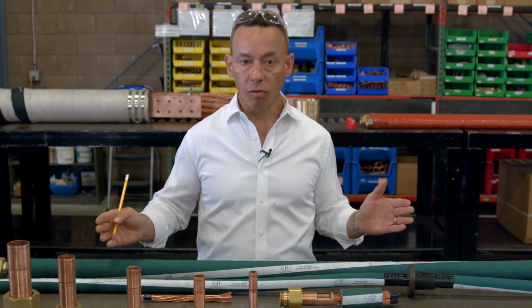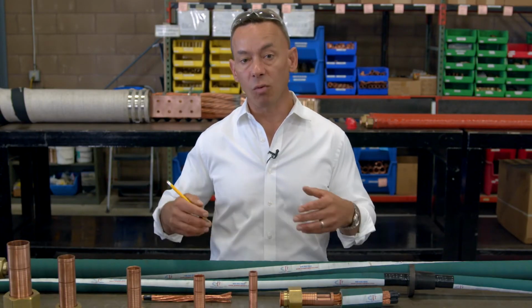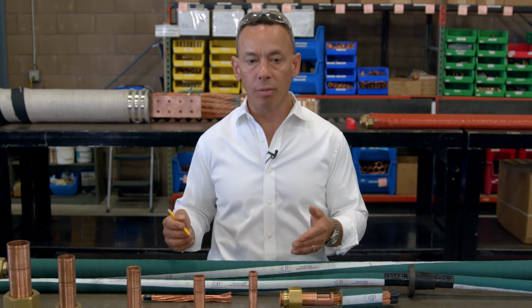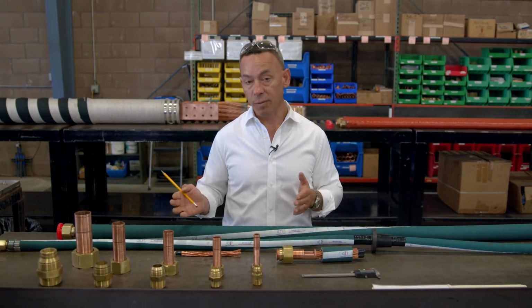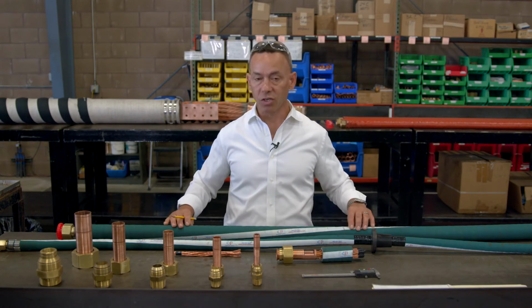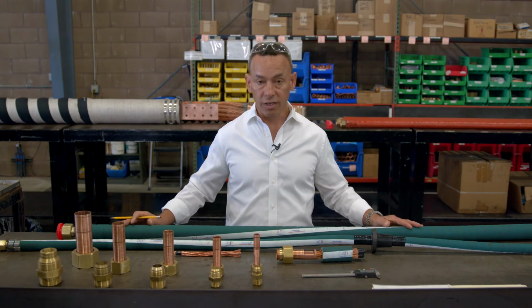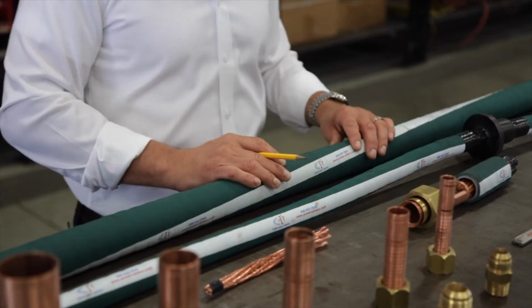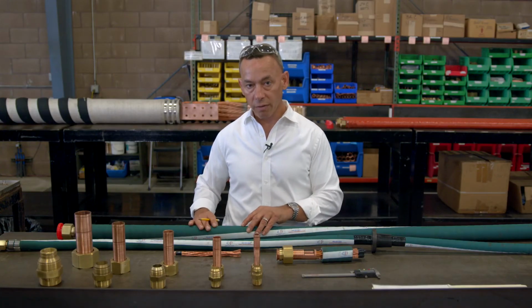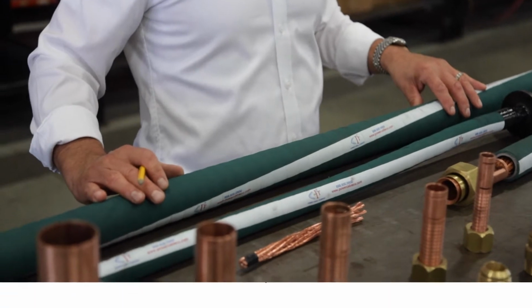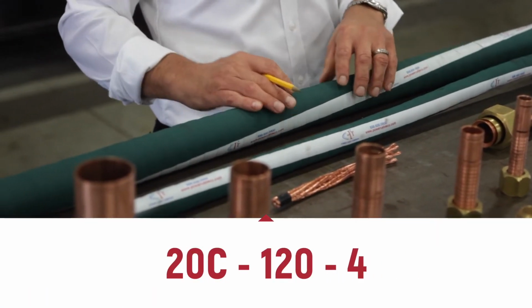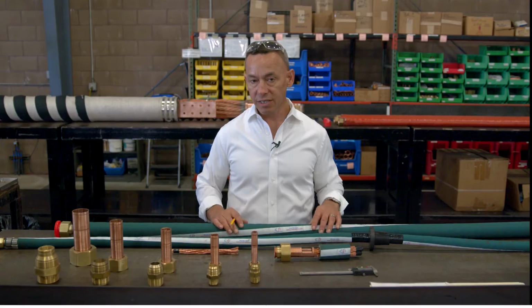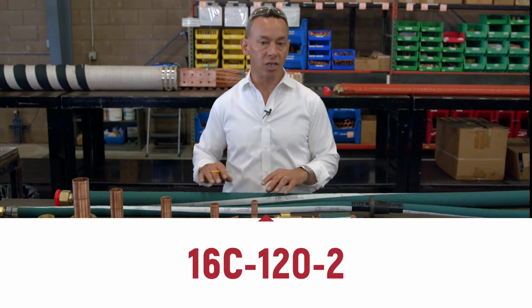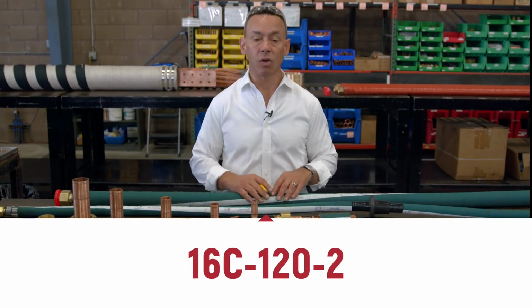So once we know the overall length and we know the ID and we've established what the cross section of the copper is, then we assign a specification to it. This cable here is a 20C and it's 120 inches long from flare to flare. So that's a 20C-120, and since it has 4 conductors running inside, it's a 20C-120-4. If it was a 16C, then we would call it a 16C-120-2, because it only has 2 conductors running inside. And that gives me everything I need to know to be able to build that cable for you.